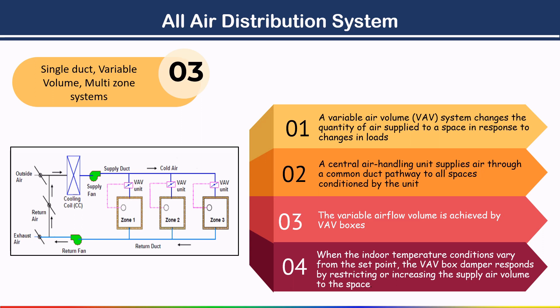The temperature of supply air to each zone remains constant, whereas the flow rate varies depending upon the load on that particular zone — that is why this system is called a variable volume system. The temperature of air supplied by the AHU may be varied occasionally for building-wide load changes, but instant control of each zone is achieved through modulation of supply air flow rate via VAV box dampers.